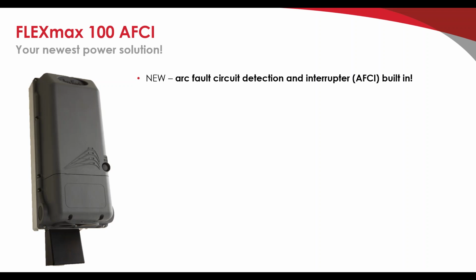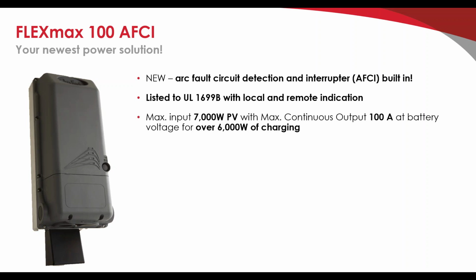So what's new on this charge controller? Well, primarily the arc fault circuit detection and interrupter is built in. Listed to UL 1699B with local and remote indication. Max input of 7,000 watts with continuous output at 100 amps and 6,000 watts of charging. What that really means is 100 amps of charging at your battery voltage. So if your battery charges at over 60 volts, then you would get over 6,000 watts of charging. But it's an easy number to put on the output.